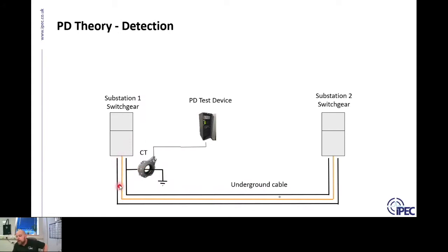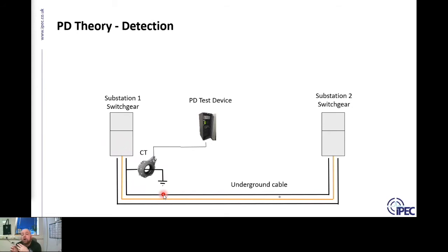On medium voltage networks, the earth may go through an insulated bushing and be terminated inside the switchgear — it's still isolated and will still carry the PD signal. Sometimes we need to take a shutdown of the termination and install the HFCT inside the switchgear termination. Alternatively, we can install the HFCT around the core of the cable. The PD signal travels along both the earth sheath and the core, and the core can actually provide a much cleaner signal, though it may be more difficult to install the sensor there.